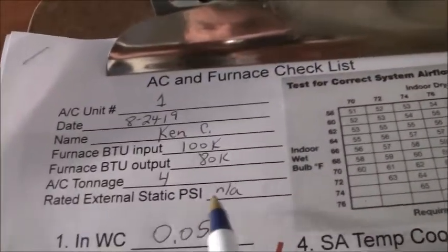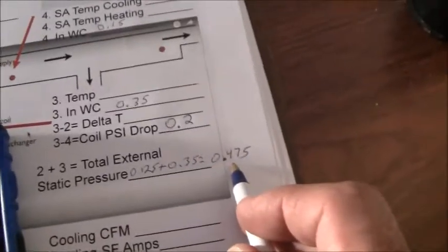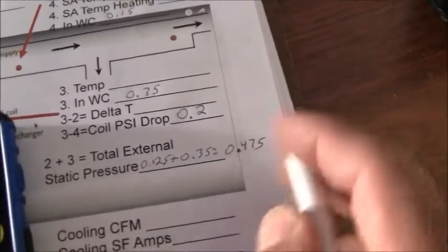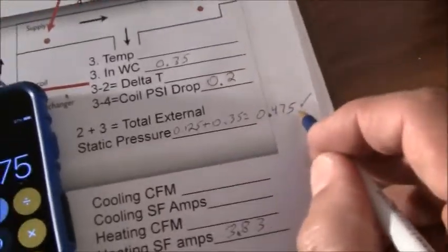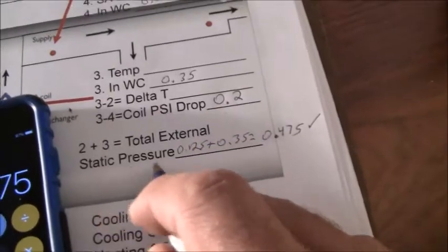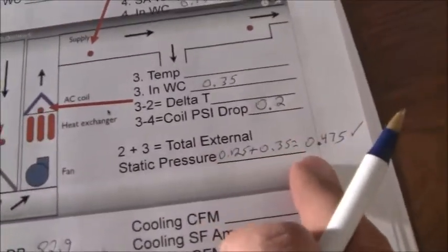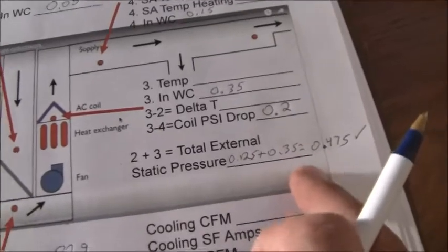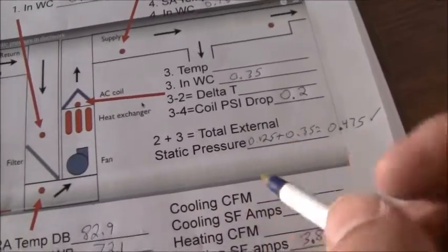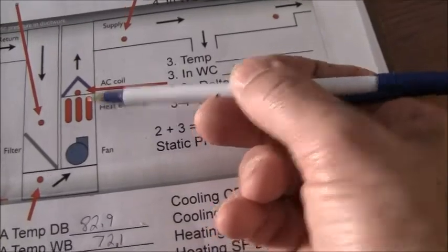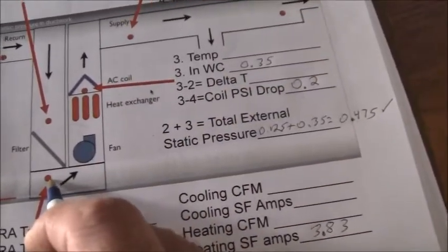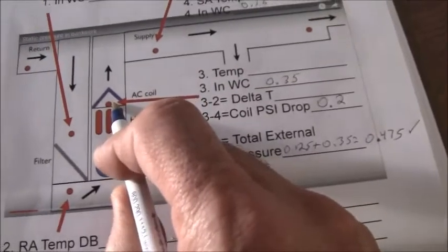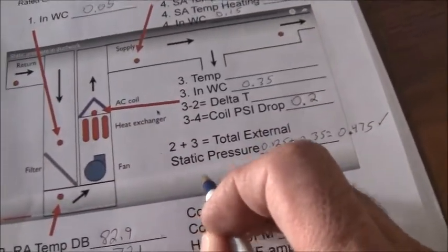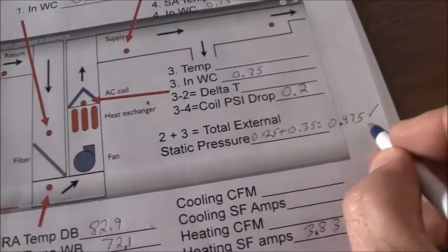So 0.475. Now my unit did not have a rated external static pressure, but if you're at a half inch or less, which is what I am, that is considered good. I don't have a restricted airflow from a total external static pressure point of view, which is how you want to review this. Now, I want to do another check. What I want to do is check external to the heat exchanger. So I want to put in a sample point low here and high here, and I want to see if that comes out at 0.475. So that's what I'm going to do right now.